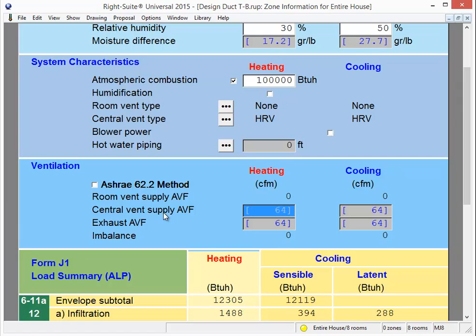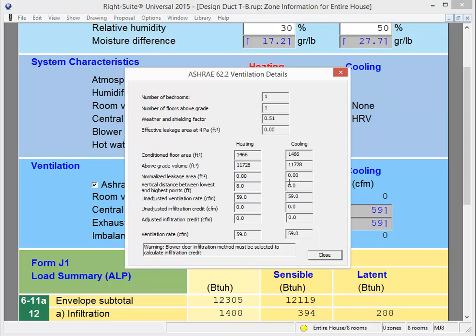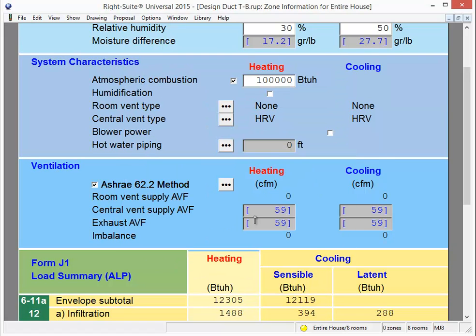What we're allowing you to do now is turn on the ASHRAE 62.2 method of calculating ventilation. By simply checking that box, the program automatically recalculates the fresh air needs of the home based on the current ASHRAE 62.2 standard. If I click on the button with three dots, I can check our math and see how it came up with that value. Something some might be interested in is whether our ASHRAE 62.2 calculation takes into account an infiltration credit — and the answer is yes. But in order to use the infiltration credit, you have to be performing a blower door test. So in order for our software to implement any infiltration credits, you have to switch your infiltration method to blower door and enter blower door data rather than simplified or detailed Manual J infiltration.